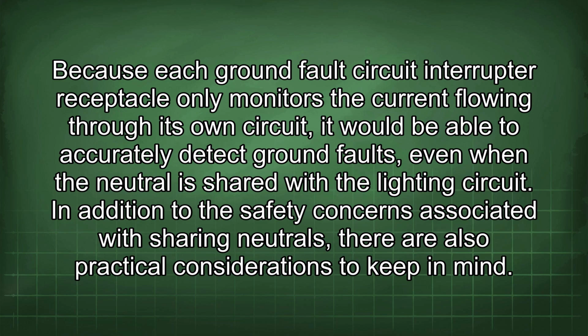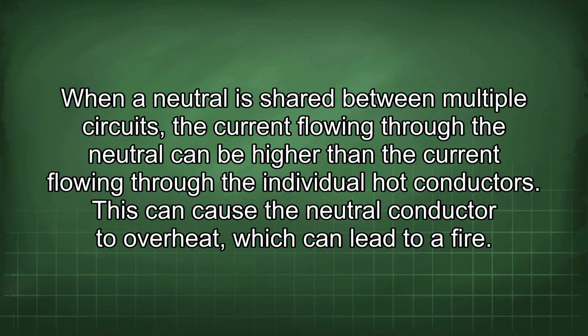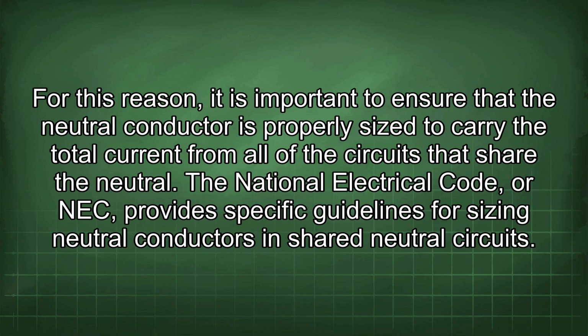In addition to the safety concerns associated with sharing neutrals, there are also practical considerations to keep in mind. When a neutral is shared between multiple circuits, the current flowing through the neutral can be higher than the current flowing through the individual hot conductors. This can cause the neutral conductor to overheat, which can lead to a fire. For this reason, it is important to ensure that the neutral conductor is properly sized to carry the total current from all of the circuits that share the neutral.